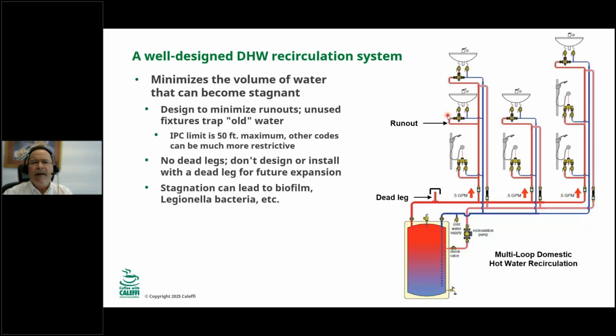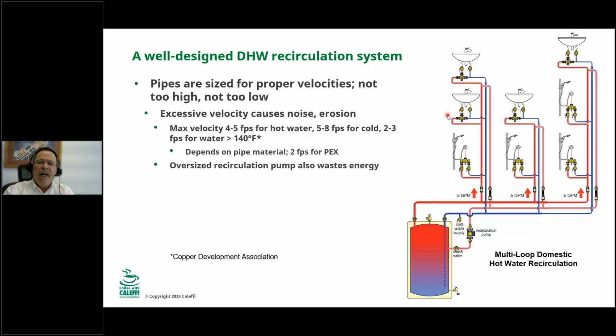Let's talk about velocity. When you size your piping, you want to have the right velocity, not too high, not too low. Let's talk about that a little bit. We know that excessive velocity will cause noise, right? I think you can, even in your own home, when you have high velocity going through a pipe, you can hear it. And what we can't see is potential erosion.